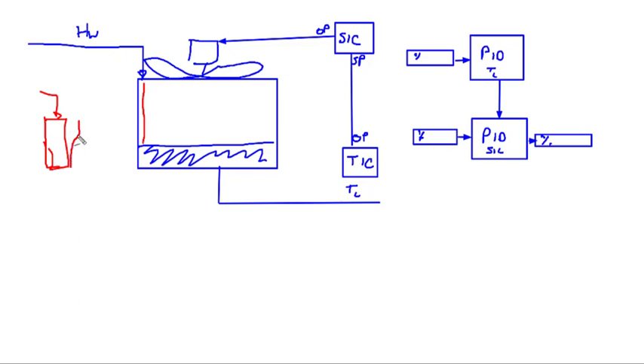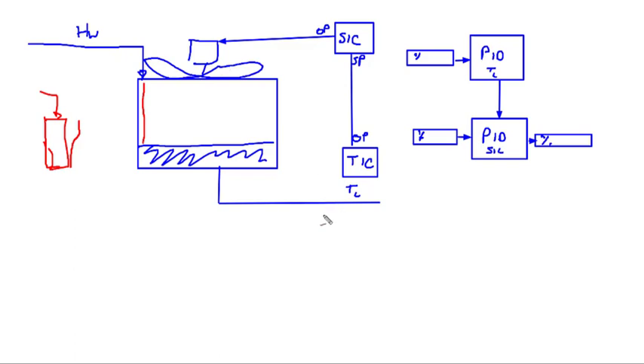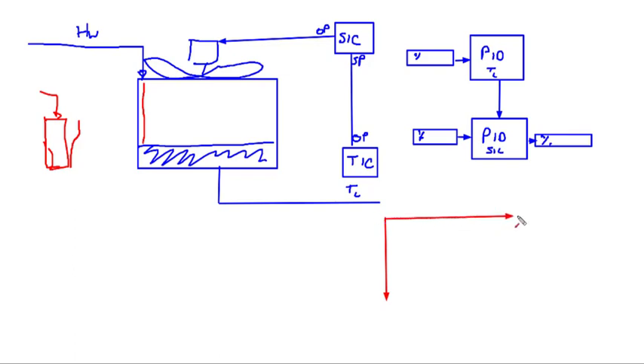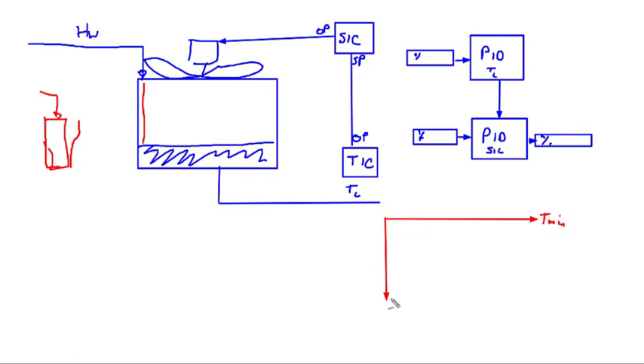This plug flow, if I change the speed, is not instantaneous. So what I did is I asked one of the young engineers to use DMC plus. We took the output of this speed control and we took the PV of the temperature. In DMC, if you plot it, it builds what I call a finite step response curve. Horizontal axis is time in minutes and the vertical axis is response in this time, degrees Celsius.